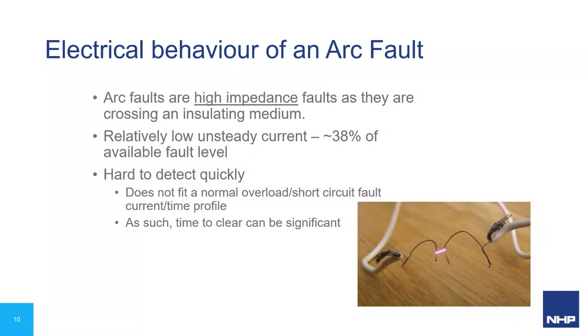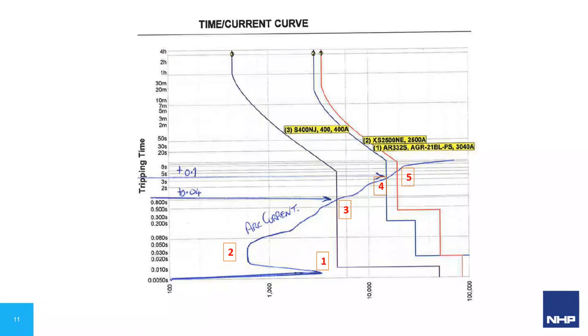So usually all of our protection in circuit breakers and fuses, et cetera, is based towards that overload and short circuit fault current time profile. As such, the time to clear can be significant compared to what we would like. So it fits into a very awkward area using that current sampling. So we've got a bit of a theoretical time current curve here.